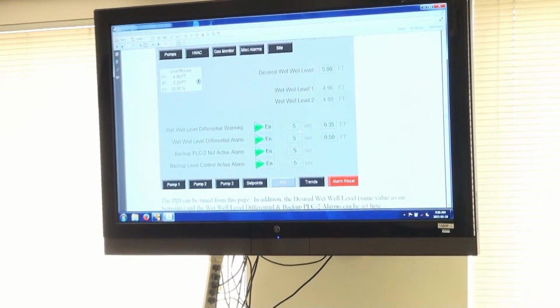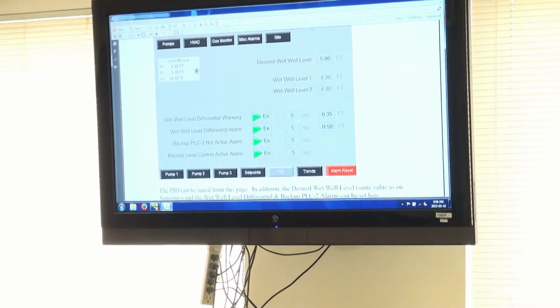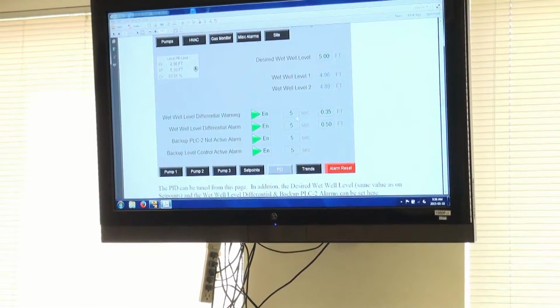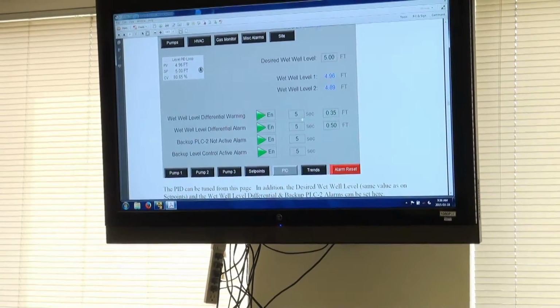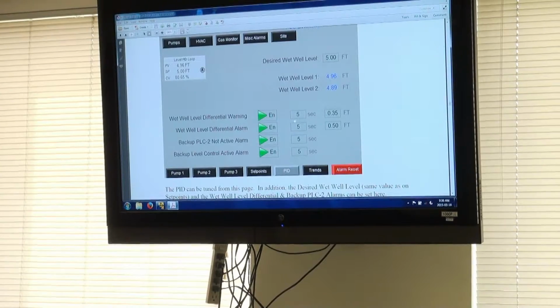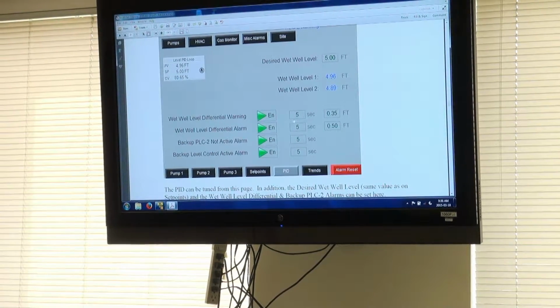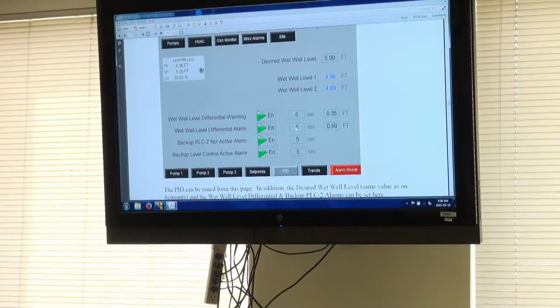We have a level differential. I do notice that we're a lot more sensitive at Montclair to a difference between the levels. I don't know if there's rags that come and float on the top or something like that, but we do tend to pick up a difference. I know when we start and stop, sometimes the A level will be higher, and then other times the B level will be higher. I wish I could find a pattern to tell you how it does it, but it really does change. I don't know if, like I said, there's something floating.